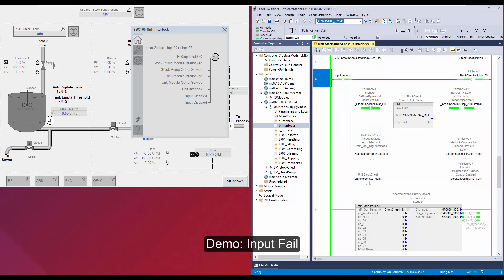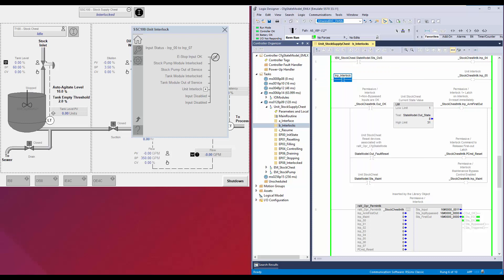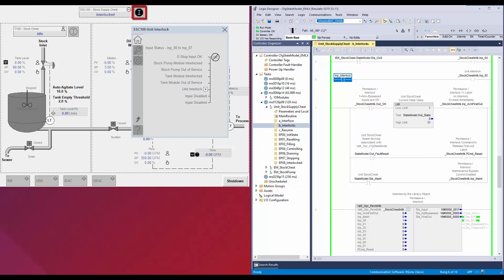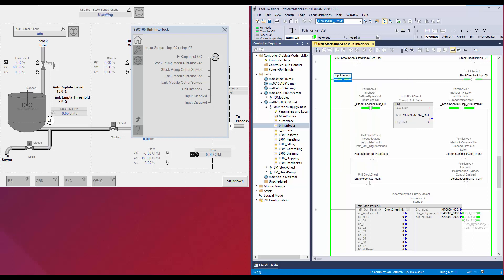For the demo, I have set all the input conditions to their OK state. I will fail the unit interlock input. You can notice the navigation object is now indicating interlock failed, and the input status in the faceplate is showing the failed condition. I will revert back the input condition. Once the input OK condition is resumed, the OK status is returned.